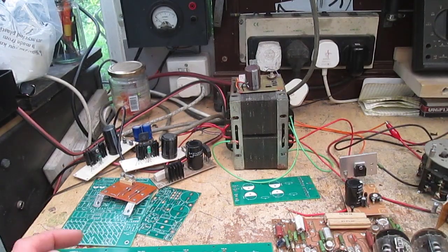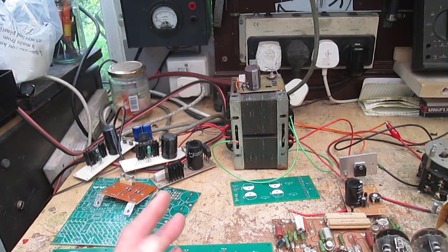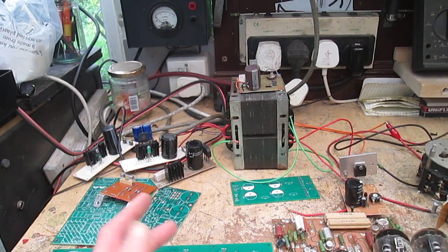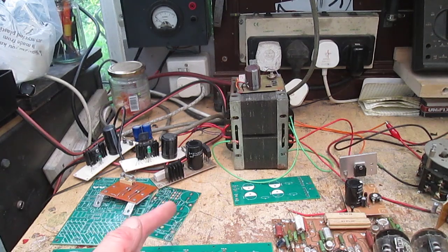Essentially all you need to test a valve within limits is a few high voltage supplies, and then you just measure the current going through the valve, and there you go. You obviously test it at certain test conditions and then compare that to the valve's data sheet, and if it is lower than specified then potentially it's a duff valve. If it's a little bit higher, all well and good.